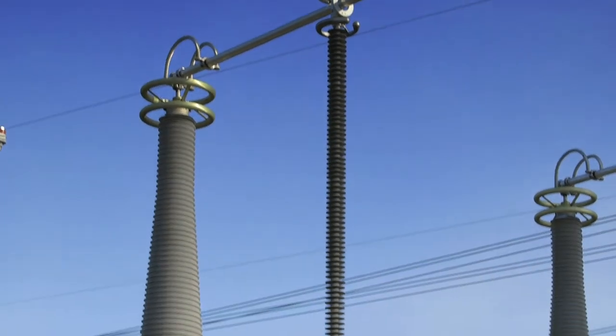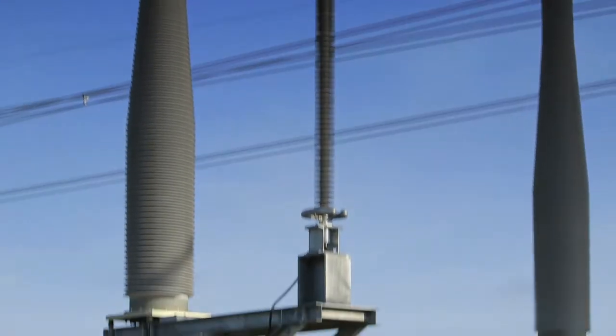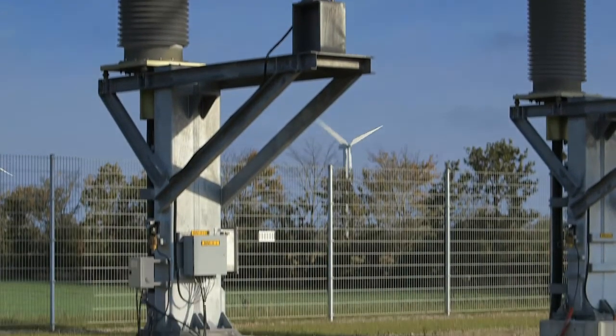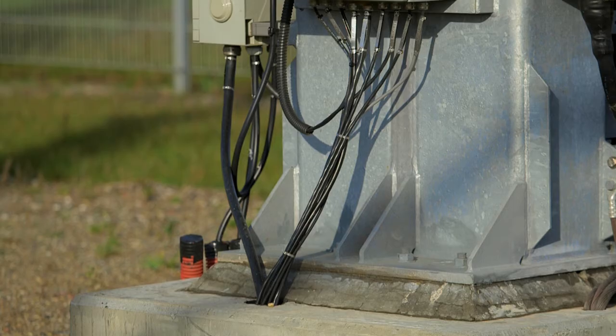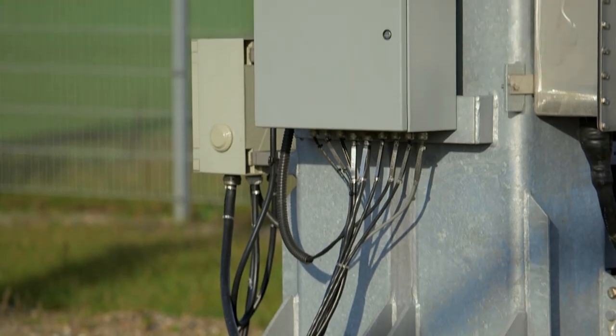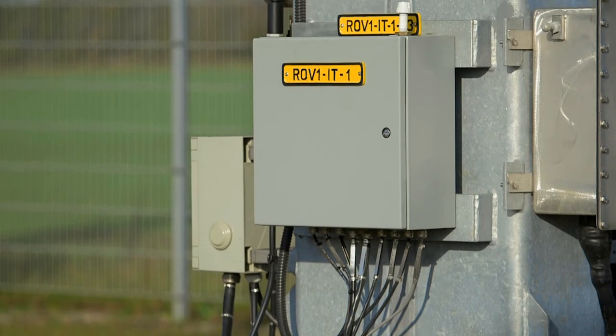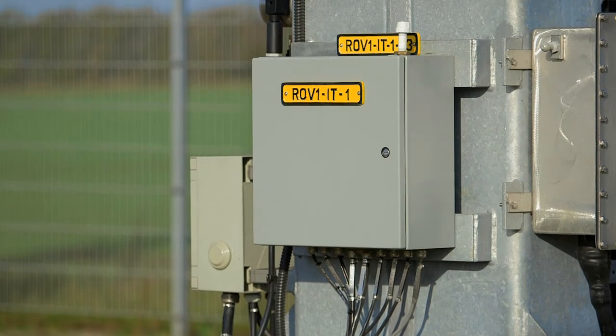We have a reduced cost of installation. In a conventional scheme, you have to have a separate stand for the conventional current transformer. Here we could actually integrate the COSI directly on the same stand, and it gave us a big cost reduction. Another advantage is that it's fairly easy to install. You don't have all those copper connections and as much cabling as you have with a conventional solution.